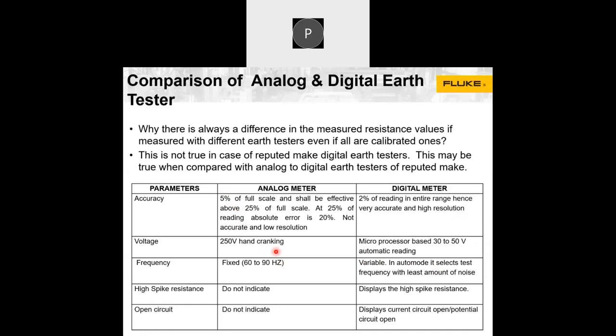We limit this voltage because, as per IEC standards, 50 volt is recommended for testing, and sometimes 250 volt also. But in the majority of applications, the precision of the voltage is very critical to ensure accuracy of your measurement.